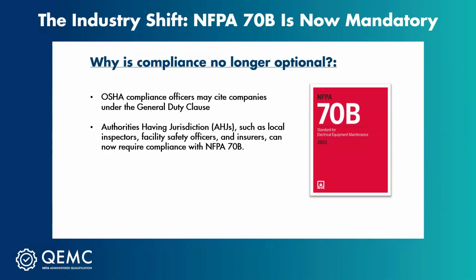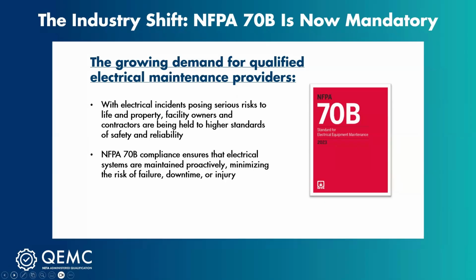Now that it's a requirement, OSHA may come in and cite companies under their general duty clause if they are not performing this maintenance. Authorities having jurisdiction, such as local inspectors, facility safety officers, and insurers, can now require compliance with 70B. We haven't heard of any facility being shut down over not performing maintenance, but inspectors do have a certain amount of authority to do that.